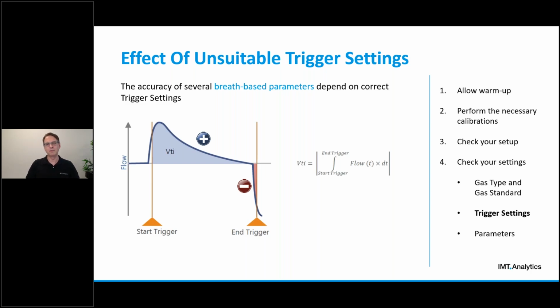Because, for example, as you can see in this slide, the inspiratory tidal volume, VTI, is calculated by mathematically integrating the flow from the start trigger to the end trigger of an inspiration phase, right? Volume is flow over time. So it starts for the VTI at the start of an inspiration till the end of an inspiration phase. And ideal trigger settings are as close as possible to the real breath phase transition. So it should actually be here and then here.